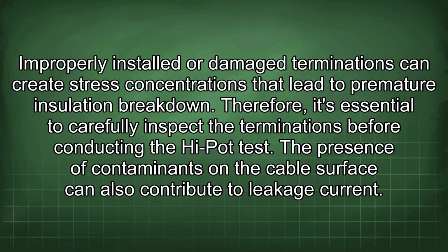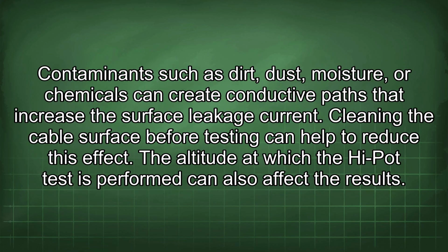The presence of contaminants on the cable surface can also contribute to leakage current. Contaminants such as dirt, dust, moisture, or chemicals can create conductive paths that increase the surface leakage current. Cleaning the cable surface before testing can help to reduce this effect.